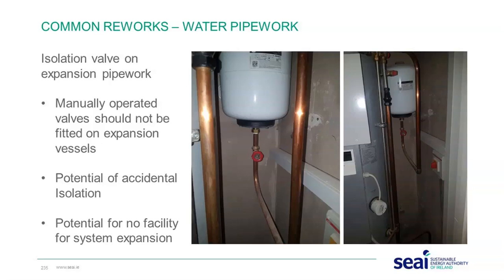Another point I'd like to bring to your attention is isolation valves on expansion vessels. Antonella had mentioned it earlier. I'm from a plumbing background myself, and I've never fitted valves on expansion vessels. Expansion vessels are there for the expansion of a system. If a system can't expand, it's going to cause problems. What's going to happen? The safety valve is going to blow, and where it blows it's causing a nuisance, causing damage to the system, pressure drops, etc.